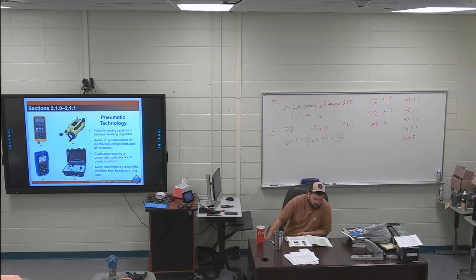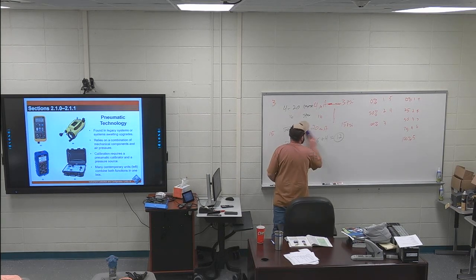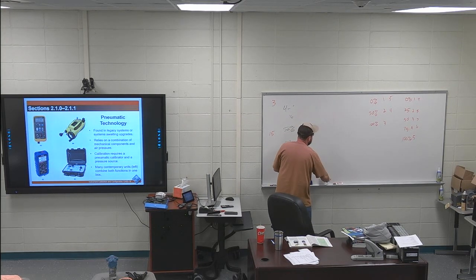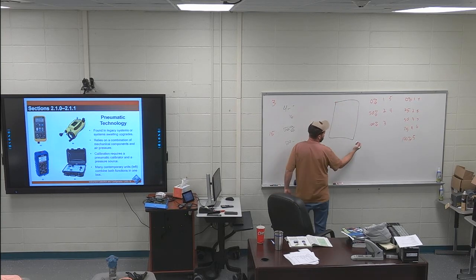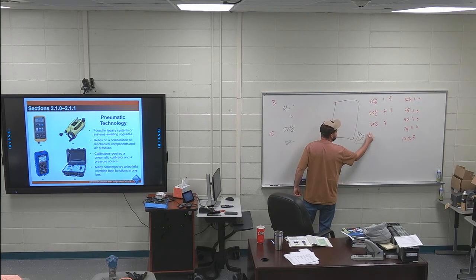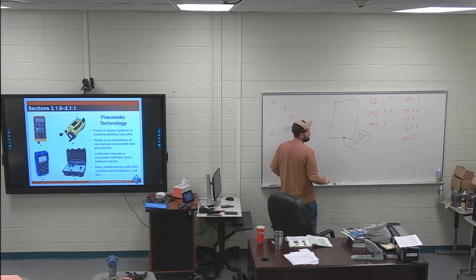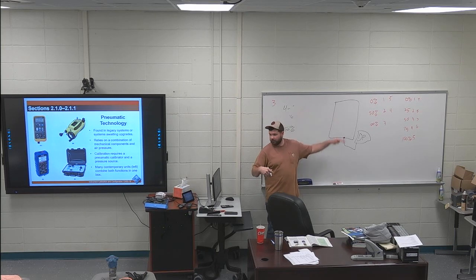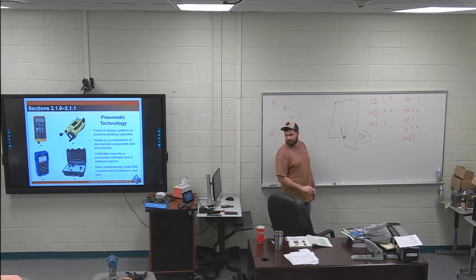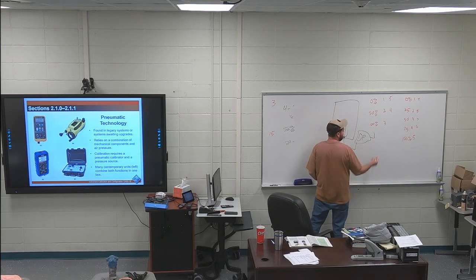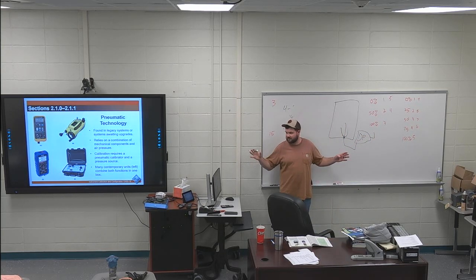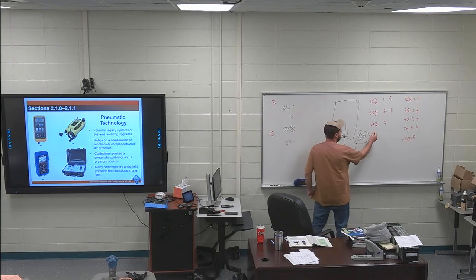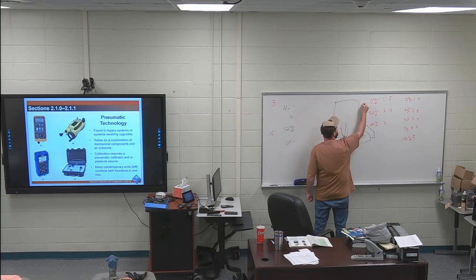The trade terms. So we've talked about a dry leg. You can use a differential pressure meter for doing level. We've talked about this before. If I had an enclosed tank, and I had my differential pressure meter right here, I have one side, this would be my high side connected to the bottom of the tank, because the more liquid I put in this tank, the more pressure that's put on the high side. And then I can have a low side. Sometimes the low side is just connected to atmosphere, and that's at 0. But if this is an enclosed tank, I can connect this to the top.